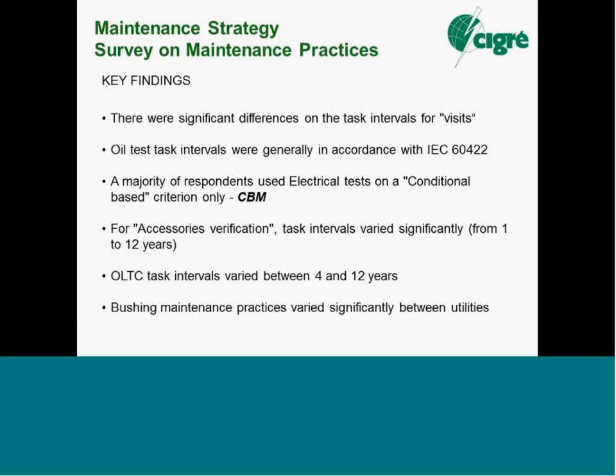There are changes, quite varied in frequency on those, but in reality we do have different taps. We have some new technologies that relax what was traditionally time-based maintenance. The number of operations is to be regarded as time-based maintenance, being bigger for the work on that tap changer. So a high number of operations means that the tap changer usually sees more regular servicing.